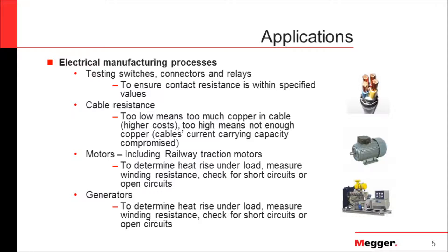Now let's talk a little more about those applications. Take motors, for example. We don't want to have adjacent coils coming short between them or open circuits, so we can use low resistance testing to look for those conditions. Additionally, when we trend the resistance values we get with those tests over time, we can identify the effects of overheating in our motor or generator.